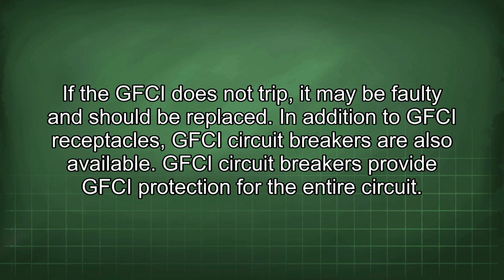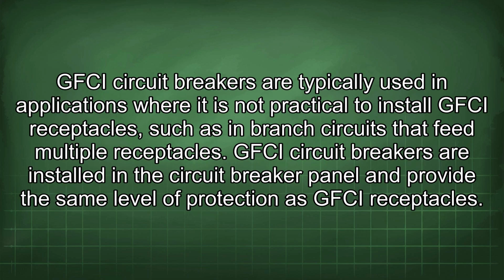In addition to GFCI receptacles, GFCI circuit breakers are also available. GFCI circuit breakers provide GFCI protection for the entire circuit. GFCI circuit breakers are typically used in applications where it is not practical to install GFCI receptacles, such as in branch circuits that feed multiple receptacles. GFCI circuit breakers are installed in the circuit breaker panel and provide the same level of protection as GFCI receptacles.